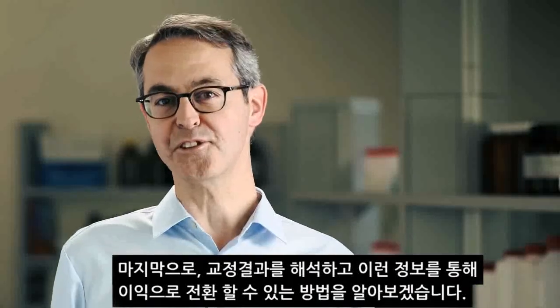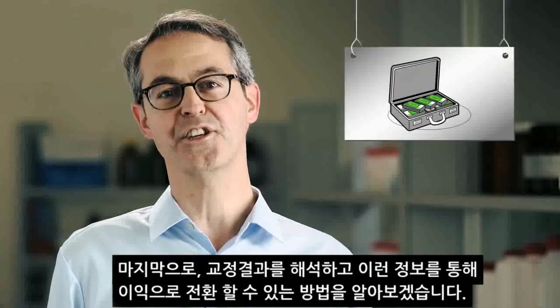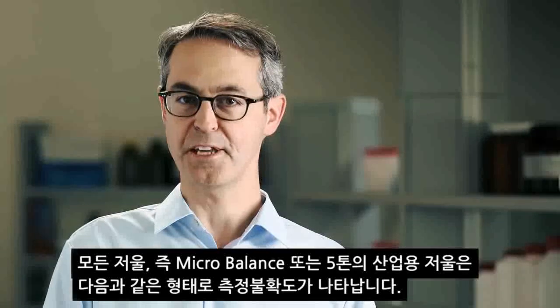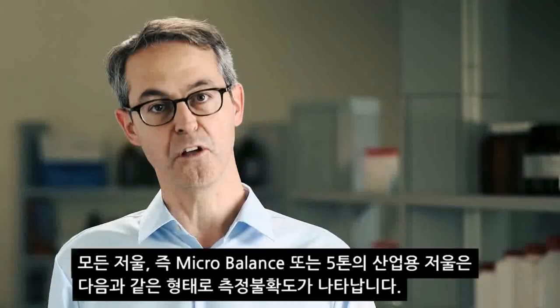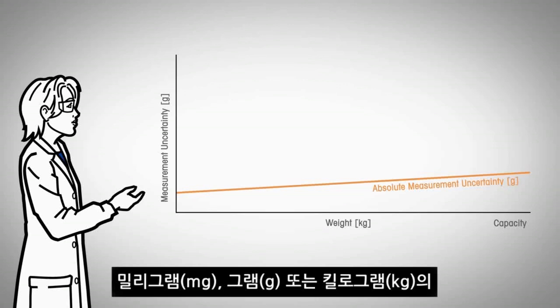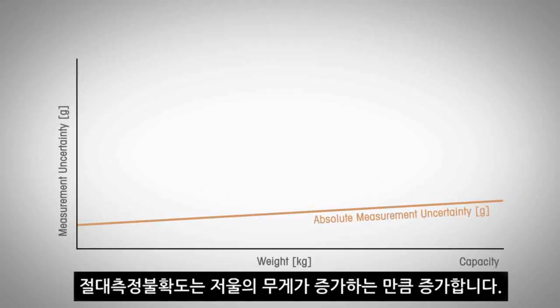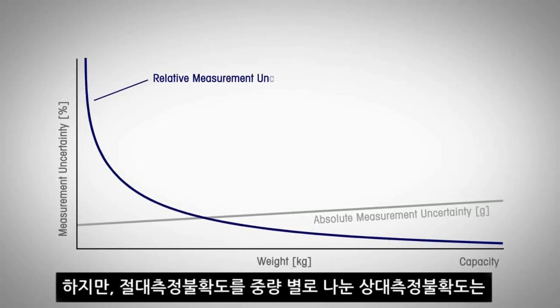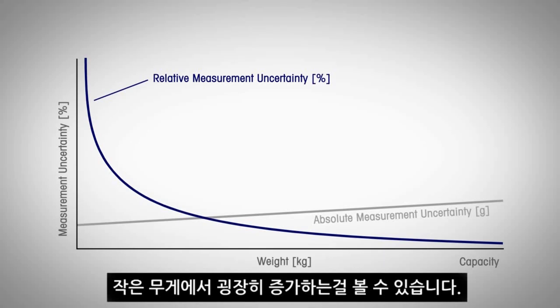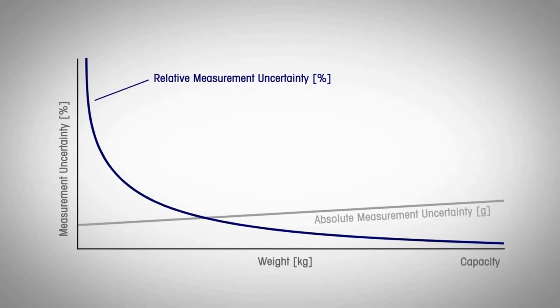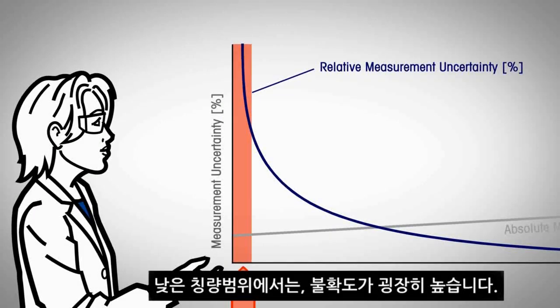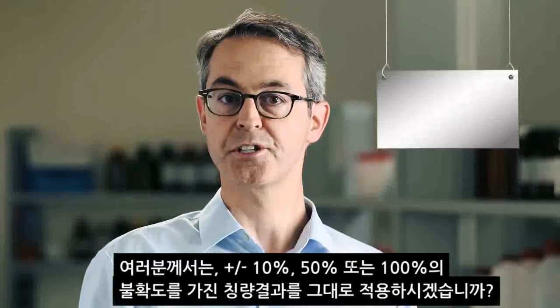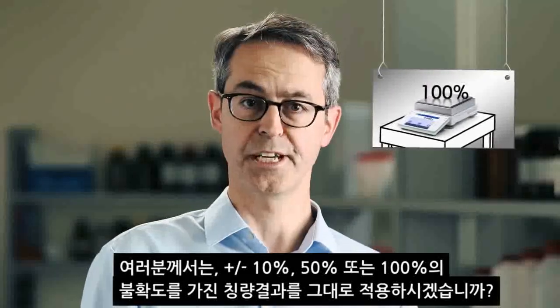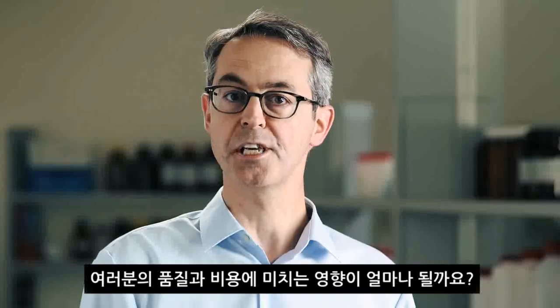Finally, let's look at how to interpret calibration results and turn this information into profit. Any weighing device, be it a microbalance or a 5-ton floor scale, shows the following behavior of measurement uncertainty. The absolute uncertainty in milligram, gram or kilogram increases as you place more weight on a scale. However, the relative uncertainty, which is the absolute uncertainty divided by the weight, increases with smaller weights. On the lower end of the weighing range, the uncertainty is so high that you cannot trust the weighing results. Would you accept a material weighed with an uncertainty of plus minus 10, 50 or 100%? What would be the impact on your quality and cost?